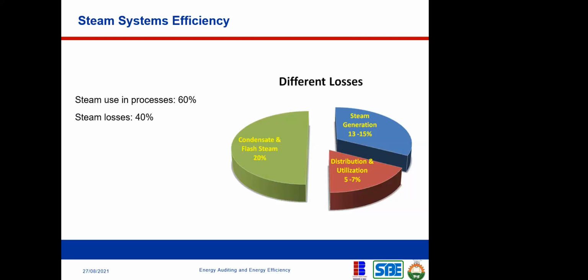So the losses in steam system can be as high as 40%. Okay, so the useful steam is about 60%. Then about 40% of it are losses. So how does this 40% losses occur? Okay, so let us look at how the 40% add up together. So condensate and flash steam account for 20%.